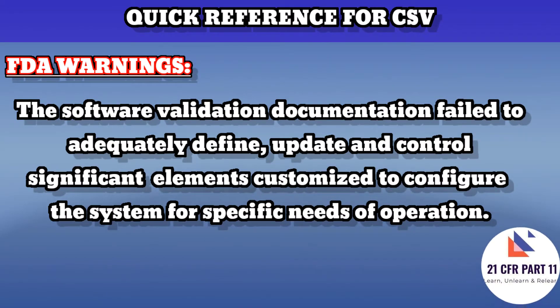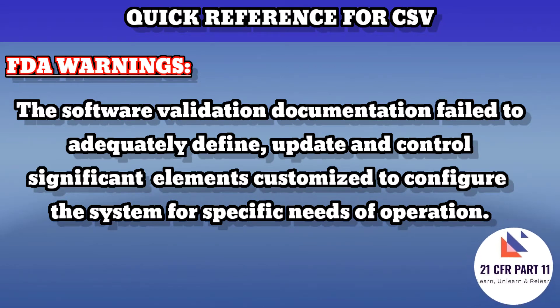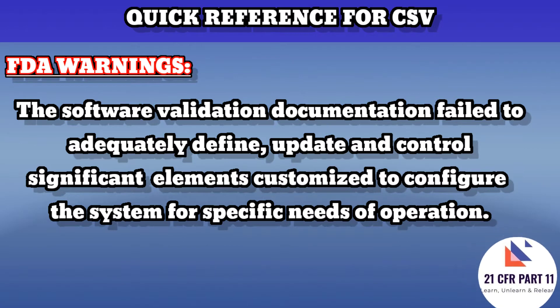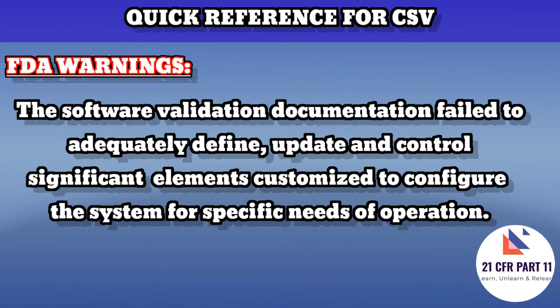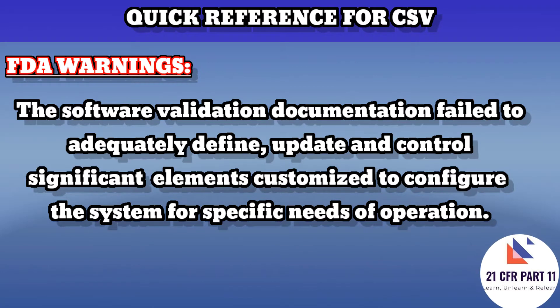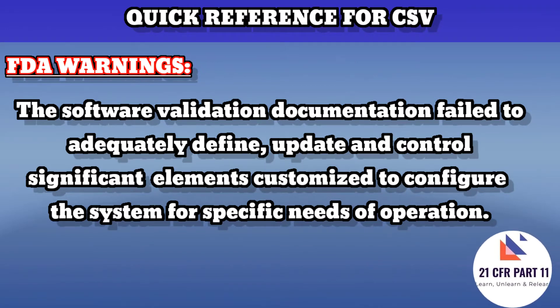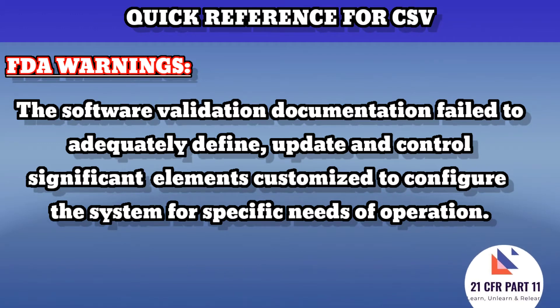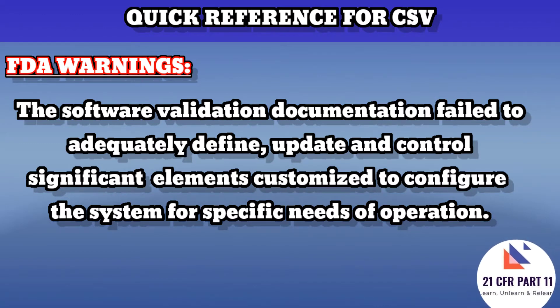Another FDA warning says that the software validation documentation failed to adequately define, update, and control significant elements customized to configure the system for the specific needs of operation. In this warning, the definition, update, and control of configuration settings not required by the computer system validation SOP was spotted. The suggestion is that you must define, update, and control configuration settings for that specific system.